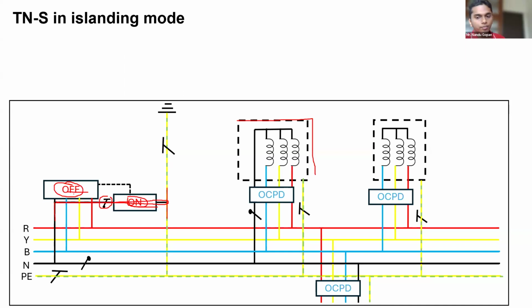So since this is connected, the PE of the installation and the source have been connected in one place. This becomes a TNS supply. So there will be only one connection, and there won't be any other neutral to PE system referencing done anywhere in the system.